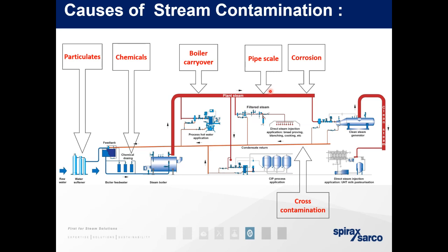So next one is corrosion. So damage to those pipes, rust from the carbon steel particulates being picked up in the pipe, and cross contamination. So if you have a leaky cooking vessel where there is a cross contamination between the condensate and the steam, that can be carried over into your feed water or then make its way into the boiler. So all of these we want to protect against.